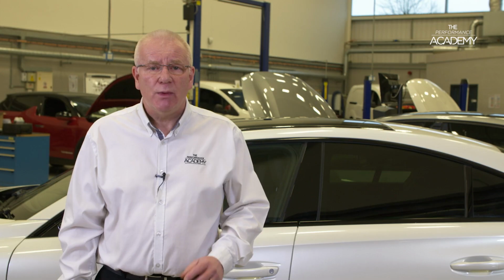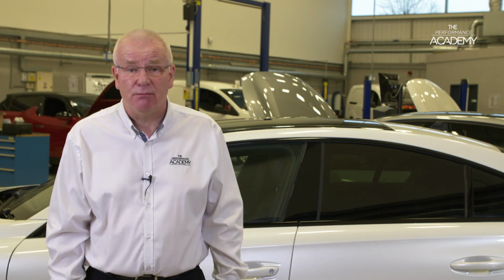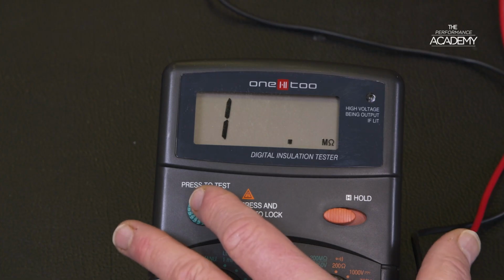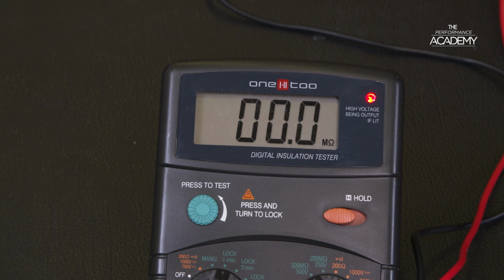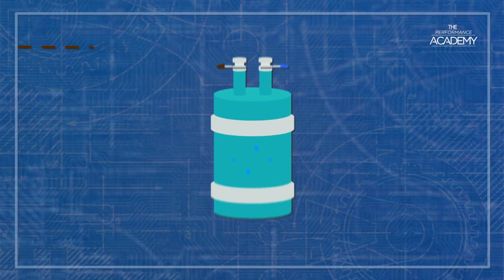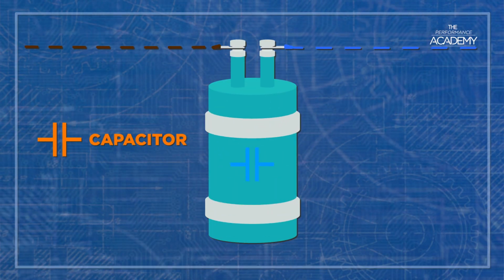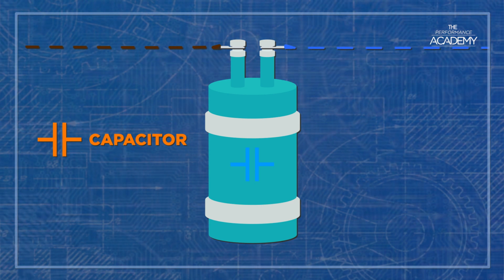To understand this more, we need to look at the difference in how an insulation tester is measuring the resistance compared to a standard multimeter. You will notice that on activation of the insulation test, the tester bleeps, in sequence with a flashing red LED. Each bleep and flash represents a pulse of electricity which builds up the voltage over a few seconds from 50 or 100 volts up to the selected test maximum, for our purposes 500 volts. It's not a constant output. In addition, any capacitance in the component or circuit being tested also generates an increasing opposing voltage.